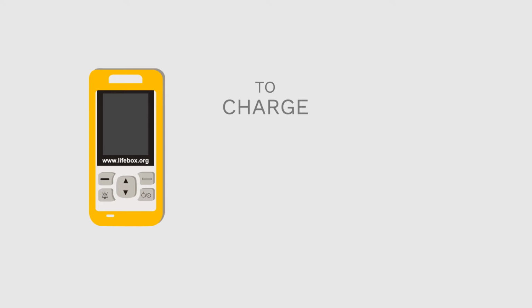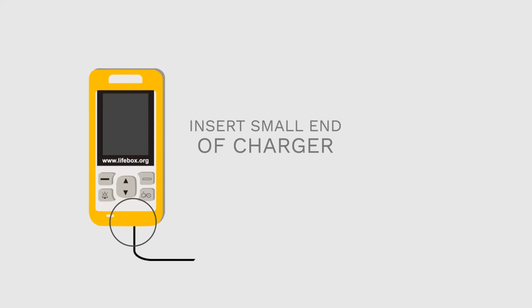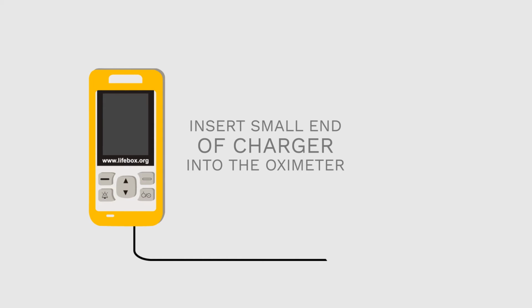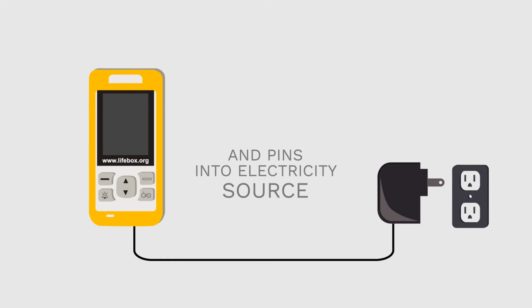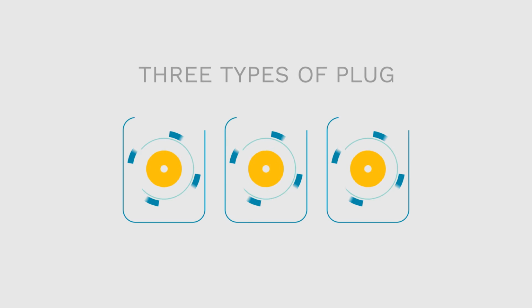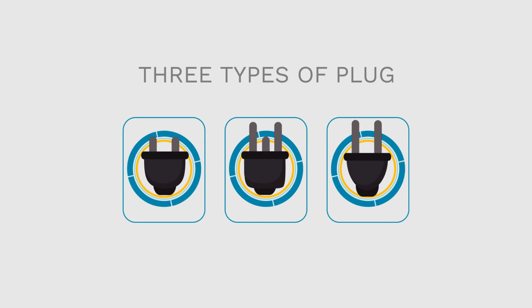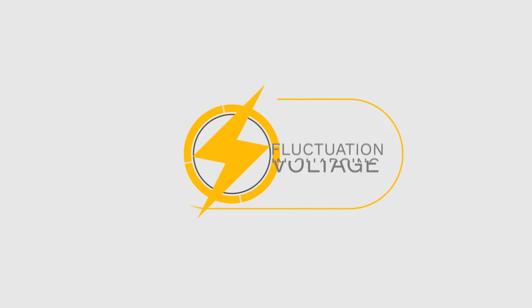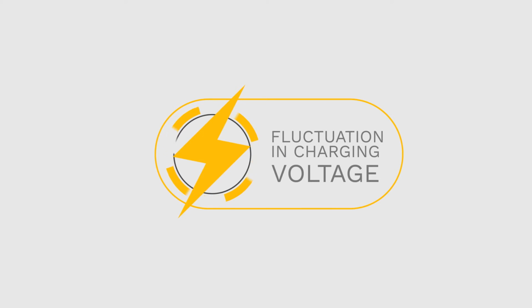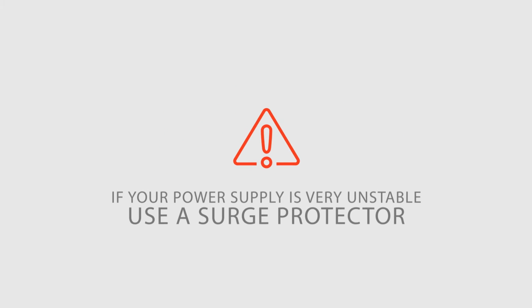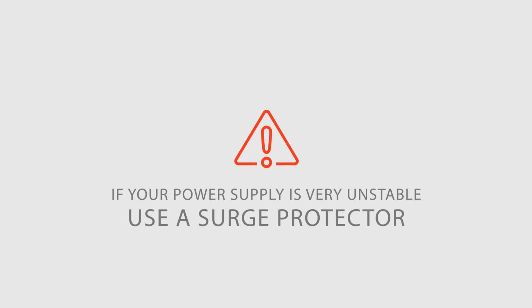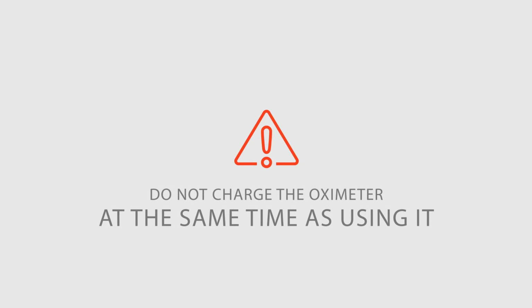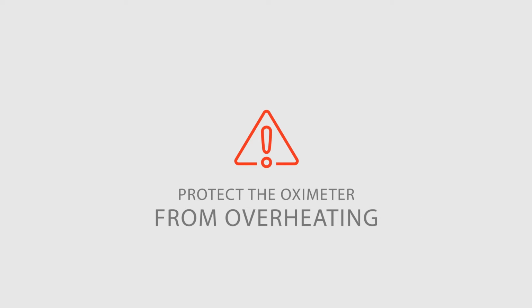To charge the oximeter and battery, insert the small end of the AC/DC charger into the bottom of the oximeter and the pins into an electricity source. The Lifebox charger comes with 3 types of plug. Depending on which region you're in, you may need to remove the pins from the base of the charger and replace them with another set. The oximeter can handle some fluctuation in charging voltage, but current surges may damage the machine over time. If your power supply is very unstable, use a surge protector if possible and do not charge the oximeter at the same time as using it. In this way, you will protect the oximeter from overheating.